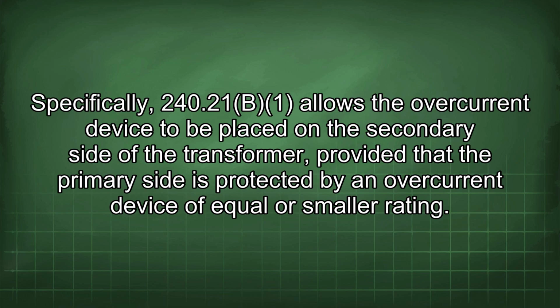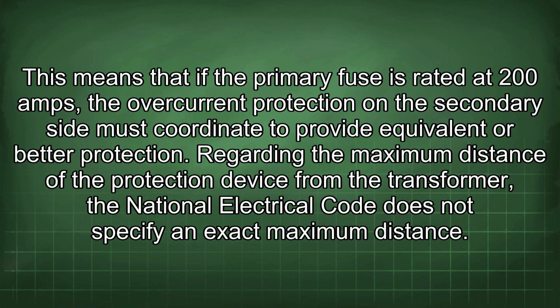Specifically, 240.21(B) allows the overcurrent device to be placed on the secondary side of the transformer, provided that the primary side is protected by an overcurrent device of equal or smaller rating. This means that if the primary fuse is rated at 200 amps, the overcurrent protection on the secondary side must coordinate to provide equivalent or better protection.